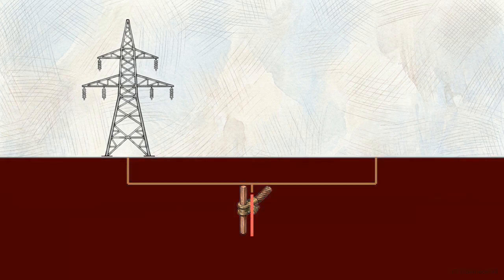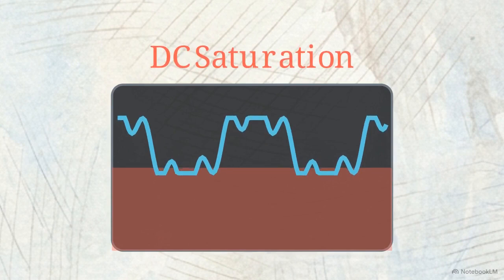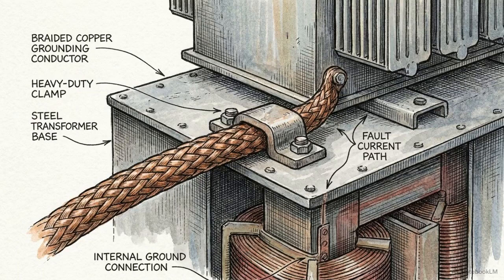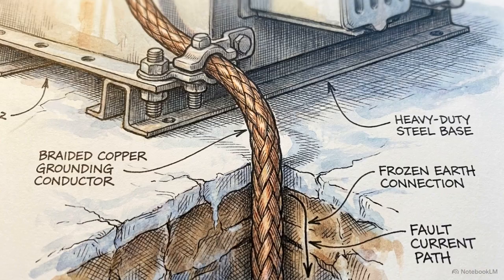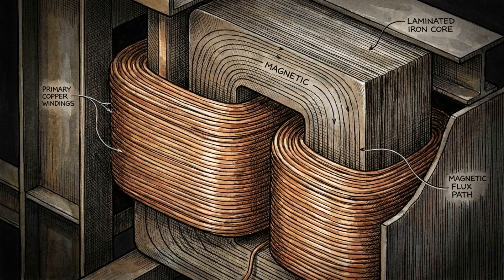The disturbance induced a direct DC current in the soil, which traveled upward through grounding wires into the transformer neutrals. Inside, this steady push of DC clashed violently with the grid's oscillating 60 Hz alternating current. The grounding wires, which were built to be the grid's primary safety release, had become the entry point for the geomagnetically induced currents. To see what happens next, we have to look inside the iron core of a power transformer, where the transfer of energy depends on a delicate magnetic balance.